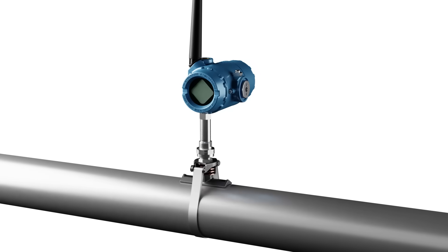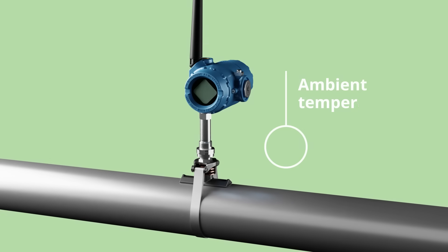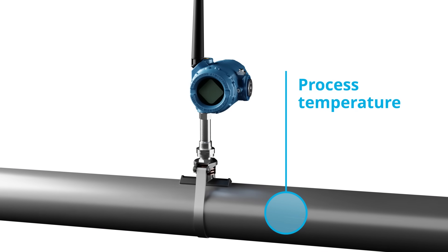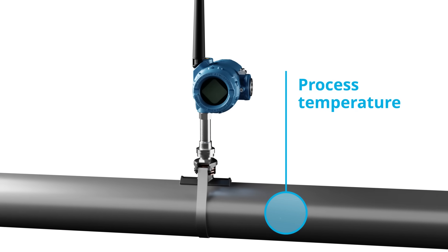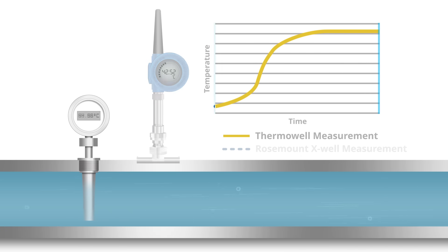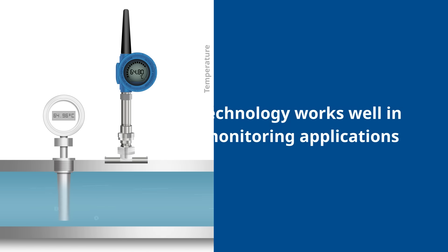Rosemount X-Well technology's patented algorithm incorporates surface temperature, ambient temperature, and thermal conduction through the pipe to calculate a real-time process temperature measurement. This technology provides reliable and accurate process temperature measurements similar to traditional thermowells.